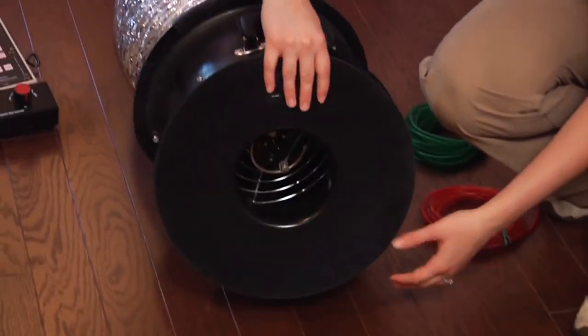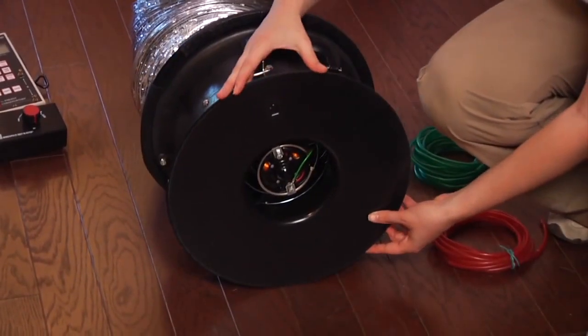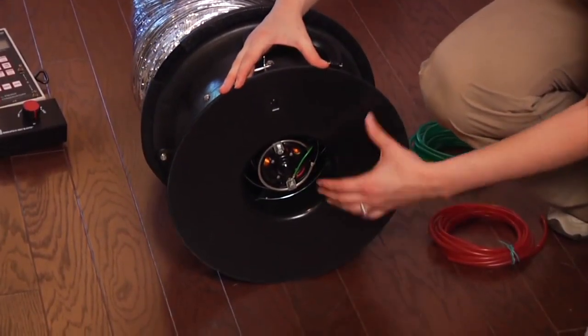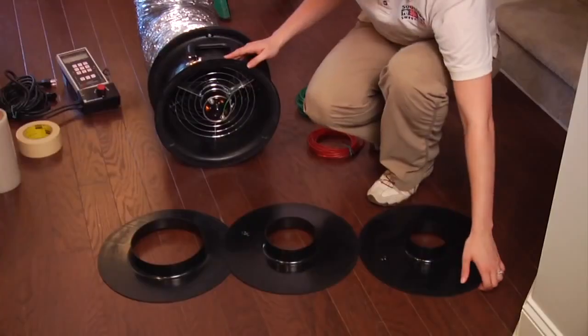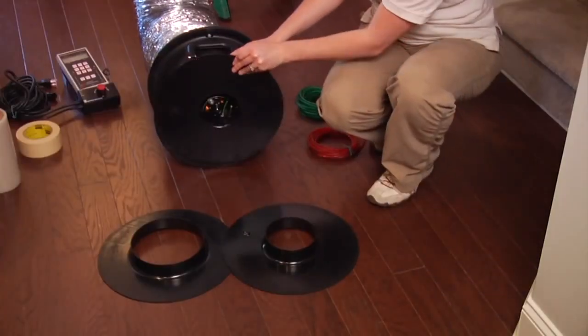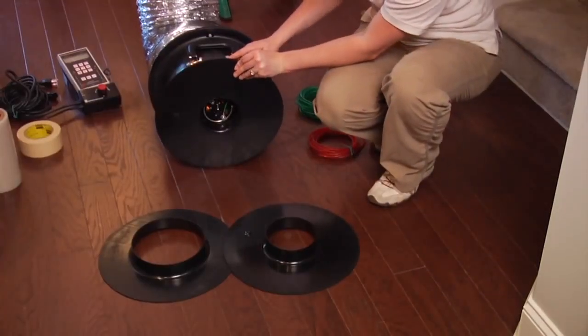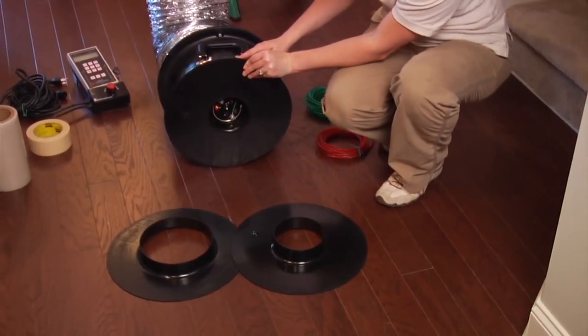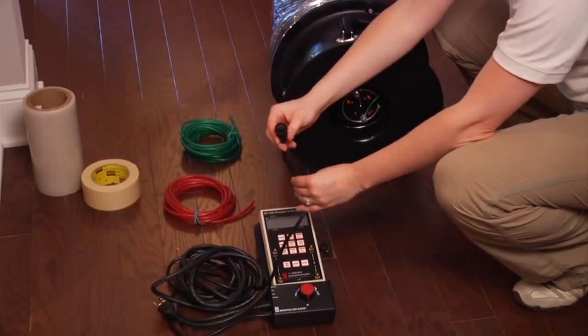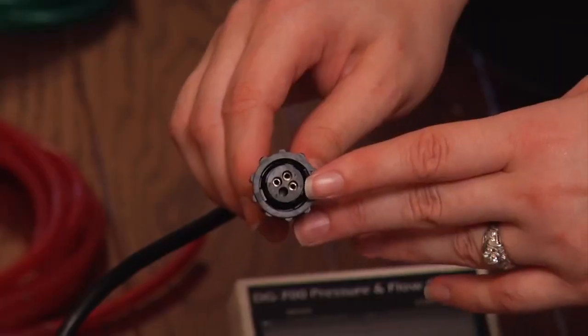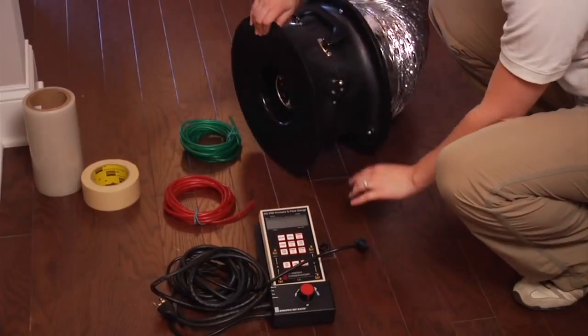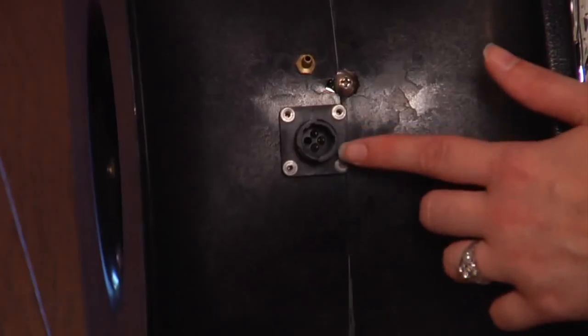Select an appropriate ring to test your duct system. Leaky duct systems may require you to use open fan, whereas tight duct systems will require you to use ring 3. For this test, we will use ring 3. Pay special attention to the military connector as the fan control has 4 holes with only 3 connections and 3 pins. Once the duct blaster is in place, you will set up the gauge.